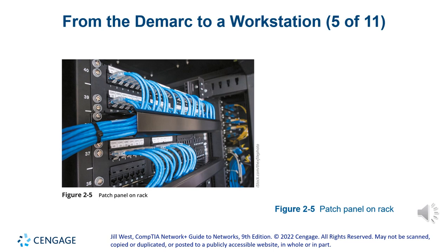They're separated by a standard unit. So that's called a U. So that's U 36, 37, 38, 39. And if you see, the patch panel on top is taking 2Us. Most of the equipment is built as either a 1U, a 2U, or a 4U, and it will take exactly that whole unit. You rarely will see something that will take half of a unit or like a 1.5. They're usually made in a way that it's either a 1U or a 2U.